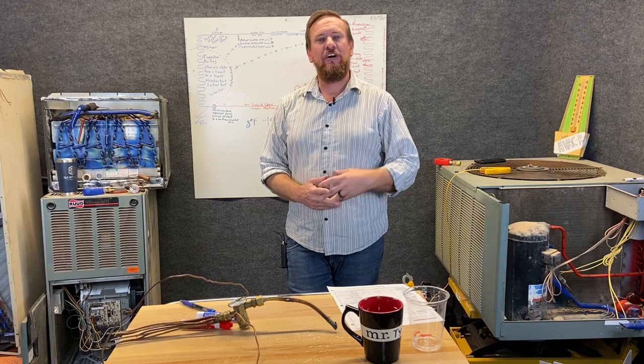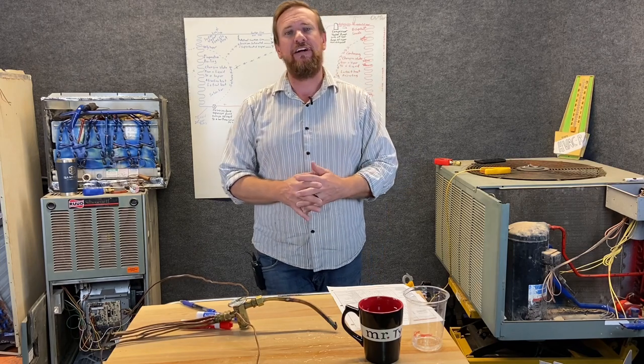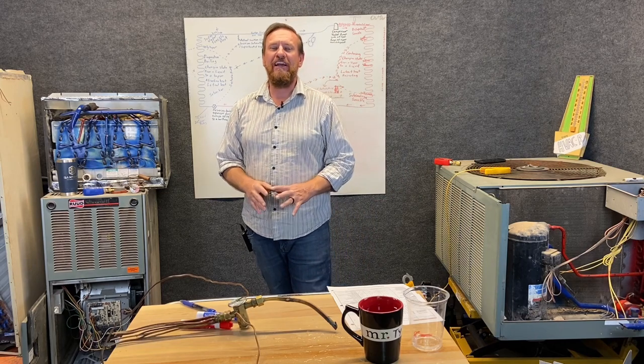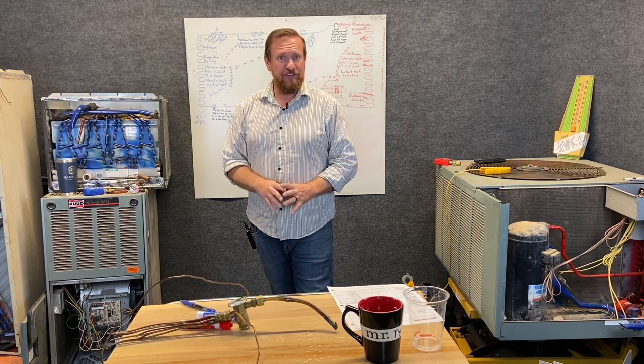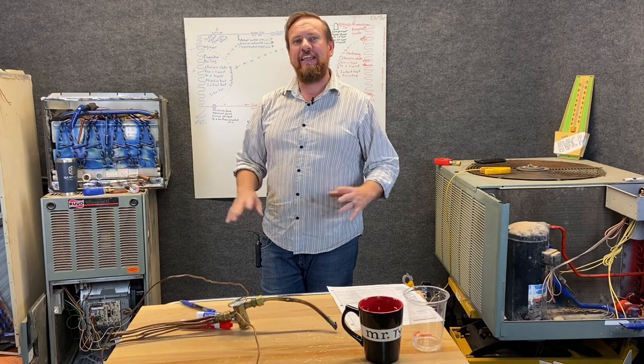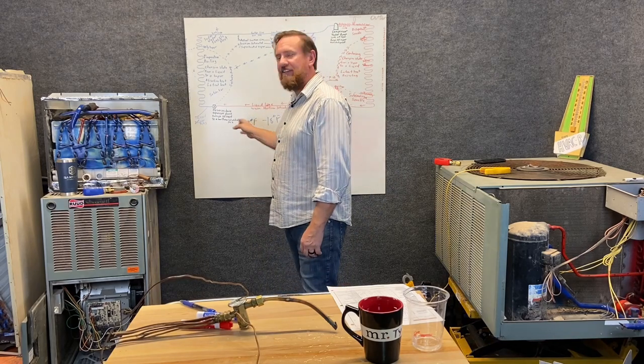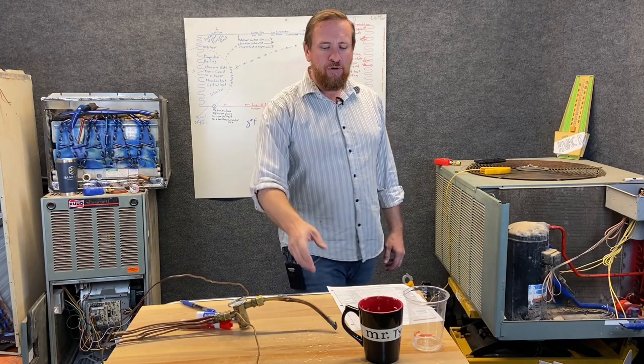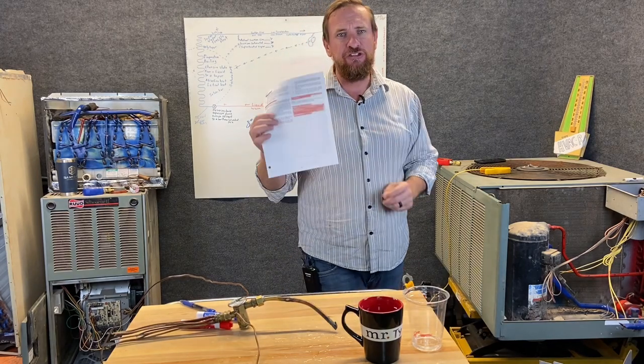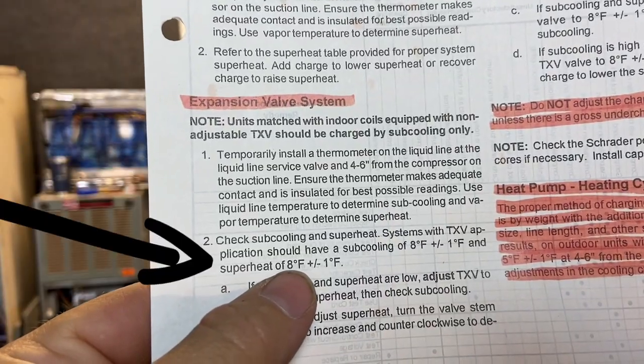Now a lot of these TXVs are adjustable. I am not going to talk about adjusting a TXV this early on because notoriously new techs try to adjust a TXV when there's nothing wrong with the settings of the old one. There's a lot more to take in before we get to actually adjusting them, but some TXVs you can adjust and set it what you want it to be. We're going to go with our manufacturer's instructions because they've specifically specified what they want. This manufacturer said they want an 8 degree Fahrenheit of superheat.